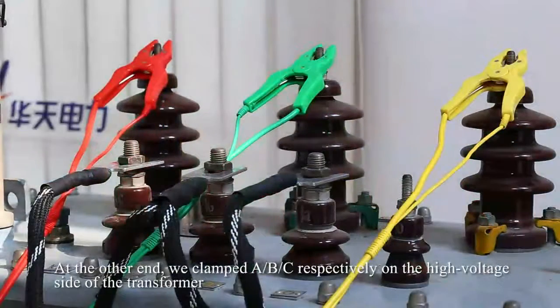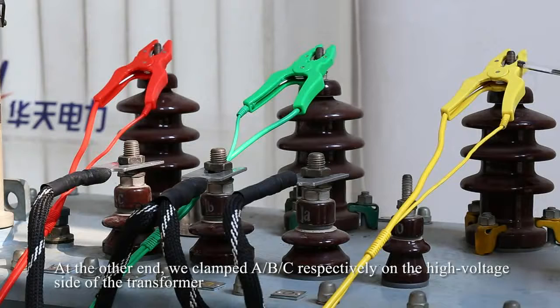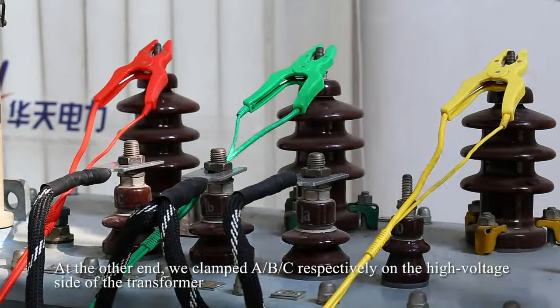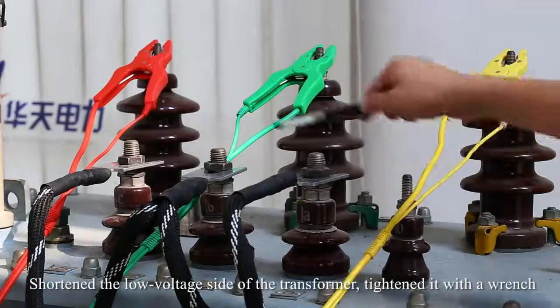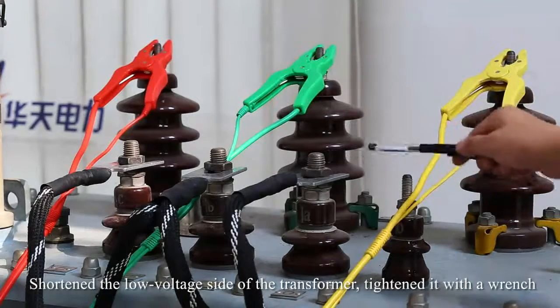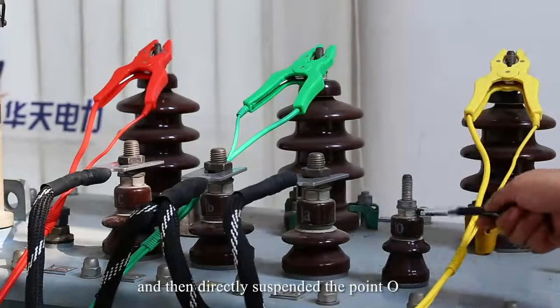At the other end, we clamp A, B, C respectively on the high-voltage side of the transformer. Short the low-voltage side of the transformer, tighten it with a wrench, and then directly suspend terminal O.